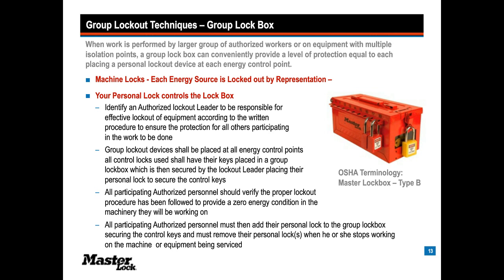Secured by the lockout leader, all participating authorized personnel should verify that the proper lockout procedure has been applied and demonstrate that they are in a zero energy condition by testing or observing testing being done of the machine. That is an absolute right. Regardless of the size of the group locking out, the ability to either test for yourself or witness the lockout testing being done is part of the OSHA standard. Okay? It gets more complicated as the lockouts get larger. We'll be talking about that.